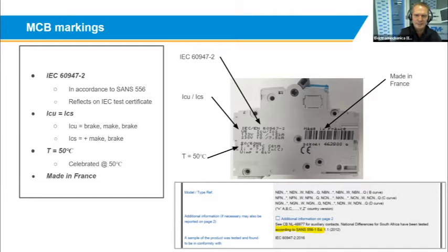By derating, we mean if you go to an installation where it is 60, 65, 70 degrees inside your board, this breaker, because of the thermal principle inside it, and I'll get to the thermal side of it, but because of the thermal technology inside it, it will start bending the bimetal strip inside, and a 10 amp circuit breaker may not be 10 amp anymore in a 65 degree application. It may only drop down to an 8 amp, 7 amp circuit breaker. So just information to know that it can do up to 50 degrees C without derating being required.